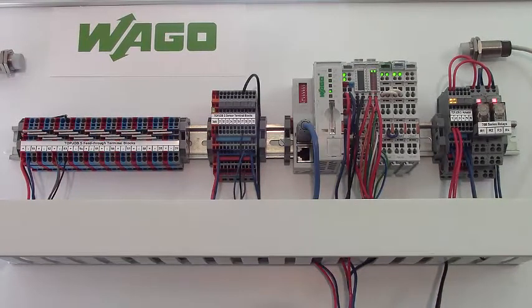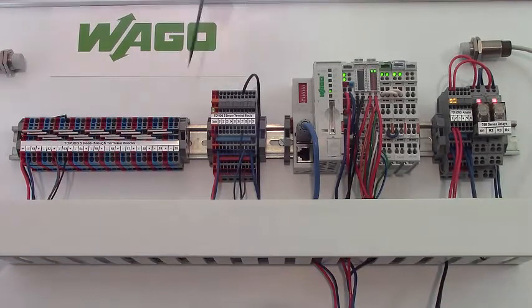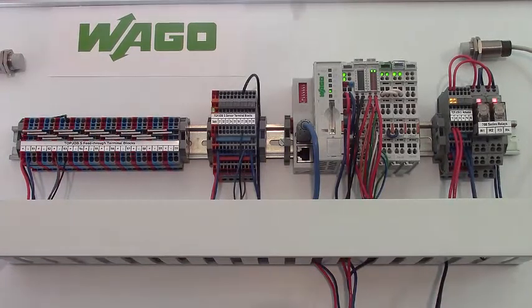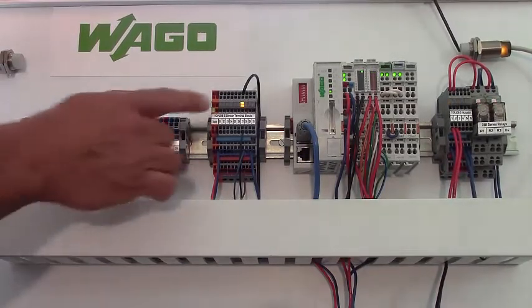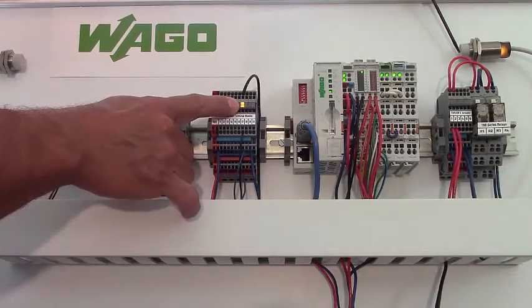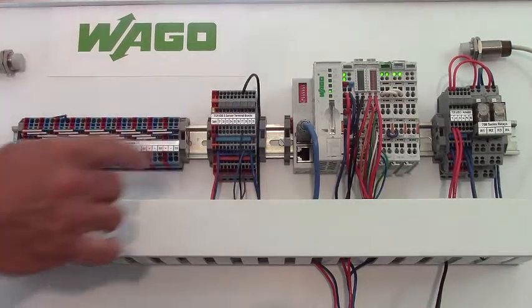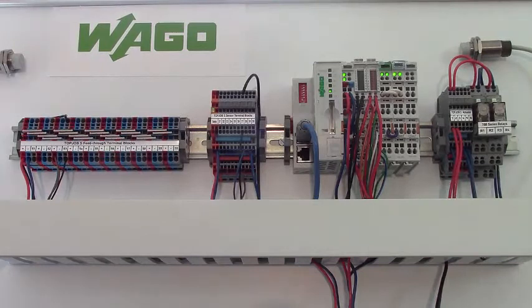So we go over to now the top job series sensor block, and you can see we get a quick indication whether or not the signal is present. So that's a great troubleshooting aid where we can split the circuit.